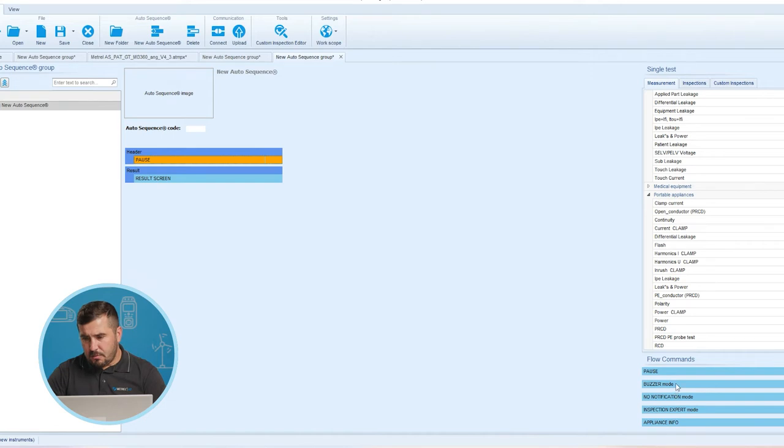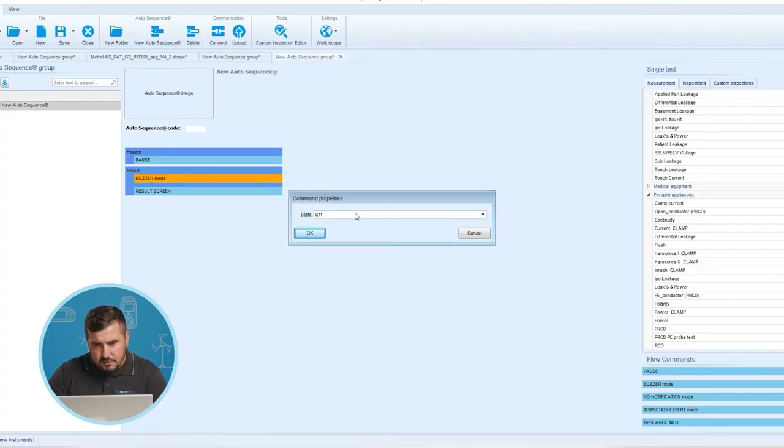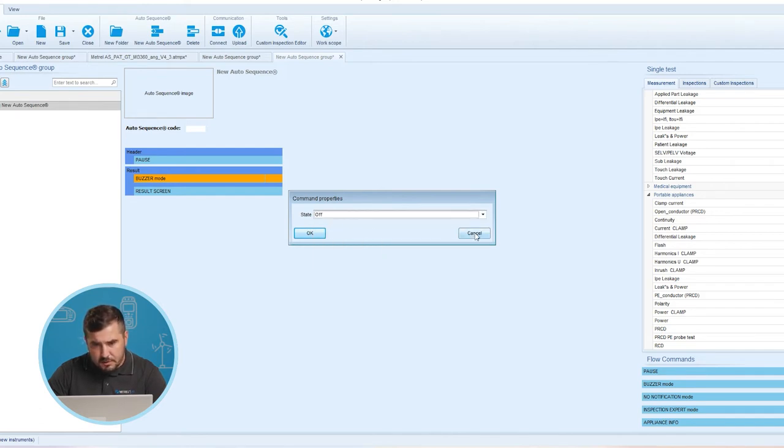The second flow command is Buzzer Mode. This flow command indicates pass/fail statuses of the measurement with beeps: for pass after the test, a double beep is performed, and for fail after the test, a long beep is performed. The beep happens right after the single test measurement. We have to set it to On to activate, or to Off to deactivate this flow command.